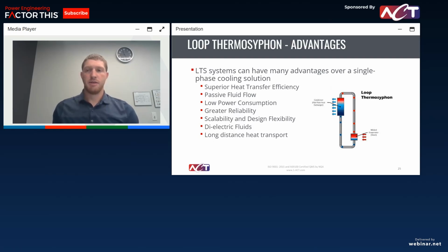And then dielectric fluids. When we're talking about high voltage components, it's very important to have that thermal, electrical isolation. So having dielectric fluids, which we'll typically use refrigerants, they're not conductive. You don't have to have an additional layer of non-conductive material between your components and the fluid like you would with water. And then lastly, that long distance heat transport, we can move the heat a long way away. So if you don't have easy access to either ambient air or your water loop or whatever it is that you need to reject your ultimate heat sink, you can move that heat a long way away to wherever that is.